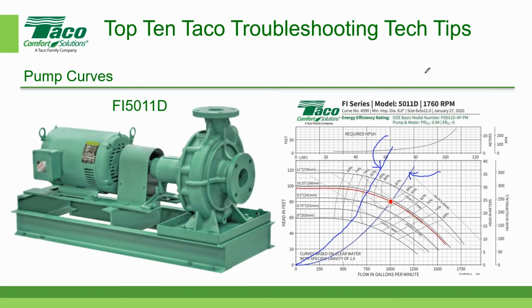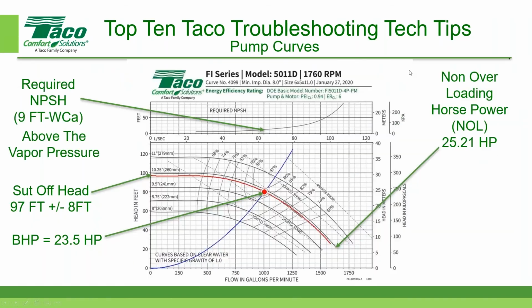All right, so let's keep going here for a moment and see if we can narrow this down. So we're going to erase this a little bit. Now remember, they sent me a piping diagram, and they also sent me some photographs. Okay, so what kind of data did they give me? Well, they gave me the pump curve, and here's all the data that's available to me from the pump curve. It says that at the design operating point at 1,000 gallons per minute and 80 feet of head, my brake horsepower is 23.5 horsepower.